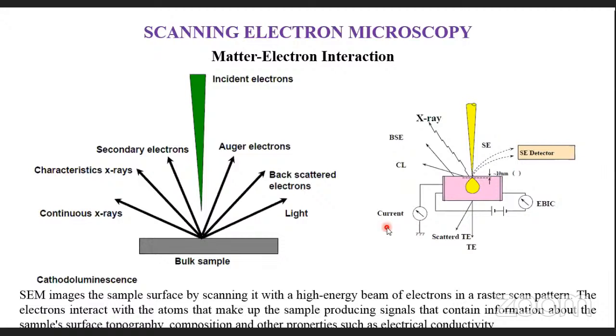We get many secondary outputs: secondary electrons, Auger electrons, backscatter electrons, light, continuous X-rays, characteristic X-rays, etc. Some electrons will transmit if your sample is really thin. In TEM, we look for transmitted electrons. But in SEM, we basically look for secondary electrons and backscatter electrons. For basic imaging we use secondary electrons, and for specialized imaging we use backscatter electrons.